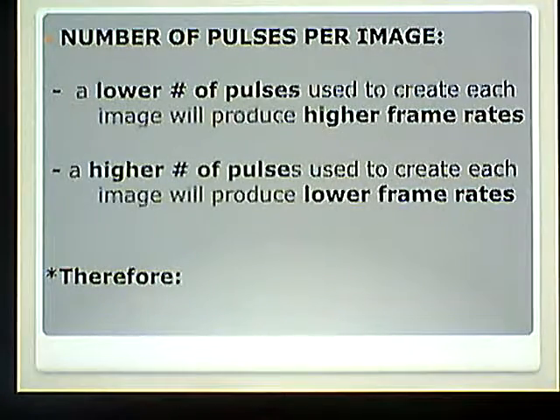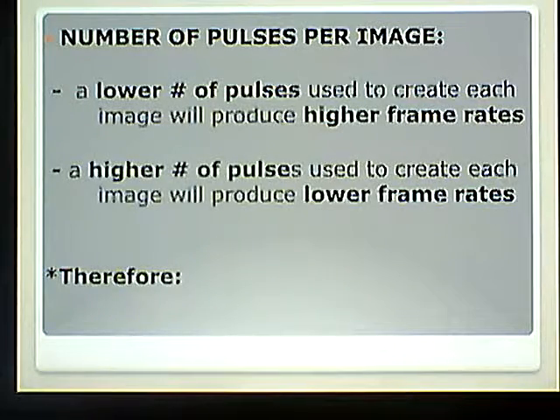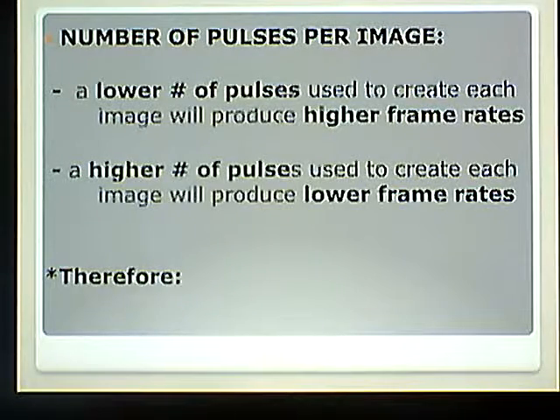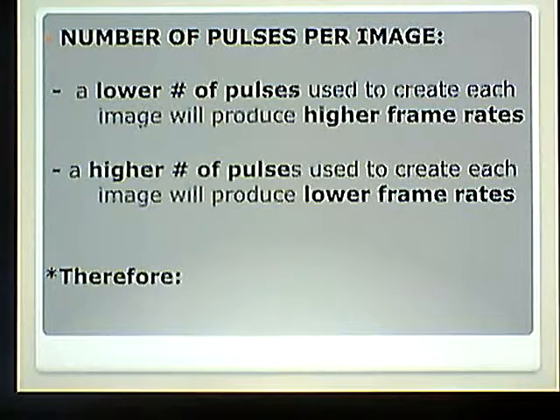Alright, so now we're going to talk about how the number of pulses per image affects our frame rate. A lower number of pulses used to create each image will produce higher frame rates. A higher number of pulses used to create each image will produce lower frame rates.